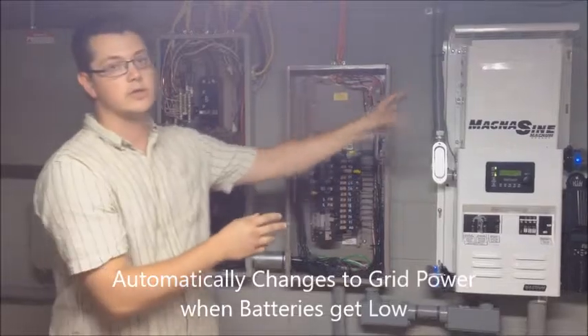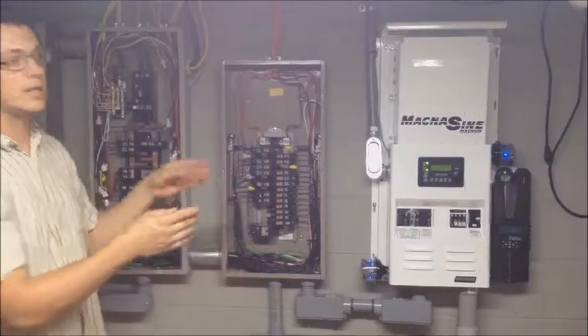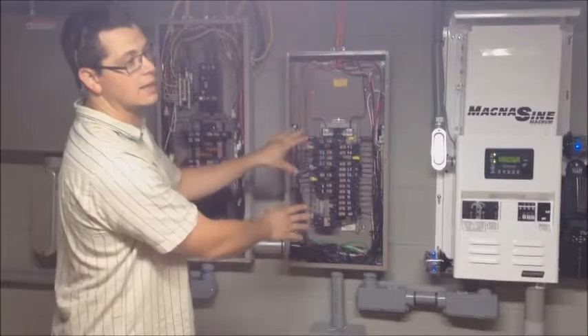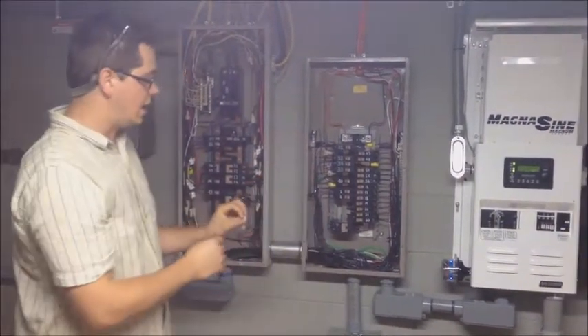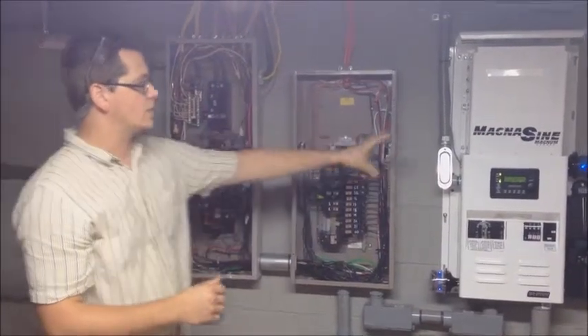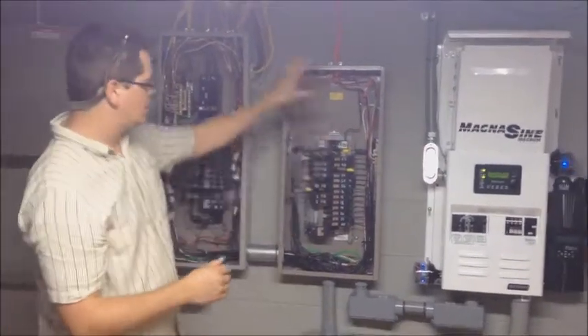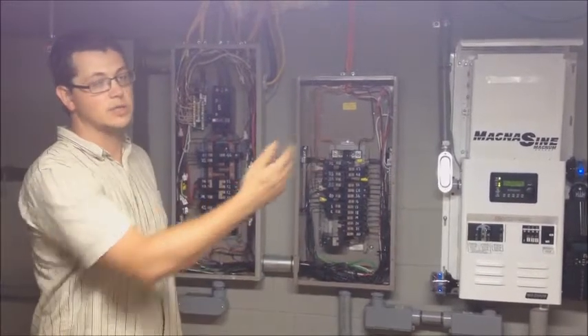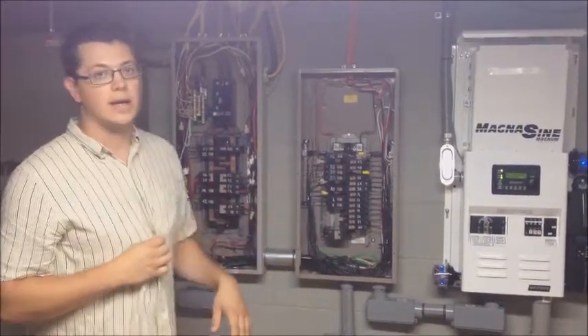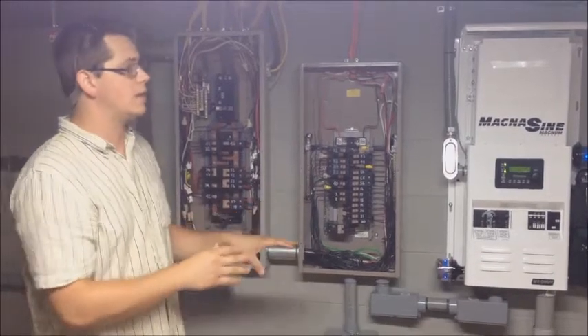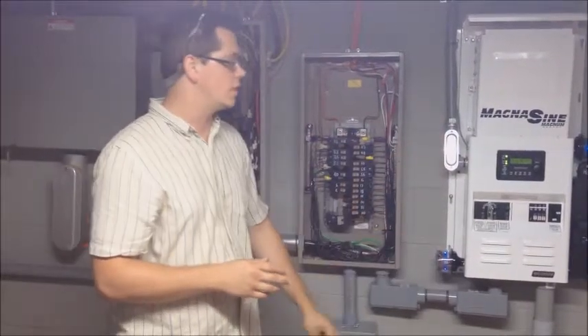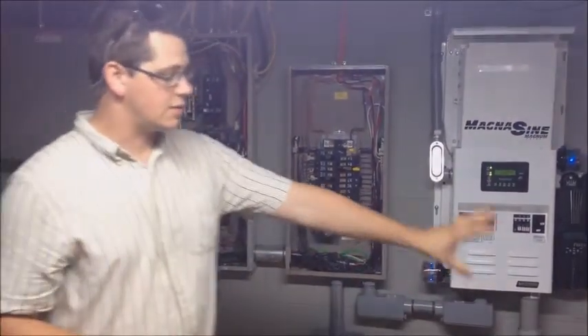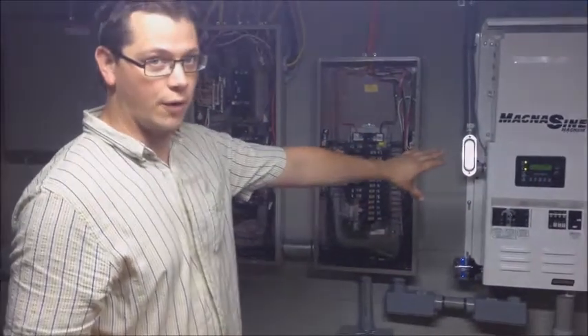So he's got an inverter charger. He's got dual redundancy, triple redundancy as far as power inputs to his dedicated panel. He can put power in here from the grid, from the generator or from the solar. And he's also generator ready. So if he ever wants to take this off and sell this house, he's already got a generator sub panel and a place where you can plug a generator in. So it's value added. It's off grid solar. It's not grid tied, but it's still got the functions in the magnum that enable it to shed load when the batteries are fully charged. And then we got our standard way we do our battery box. And you better believe she's going to bring down that power when the grid goes down.